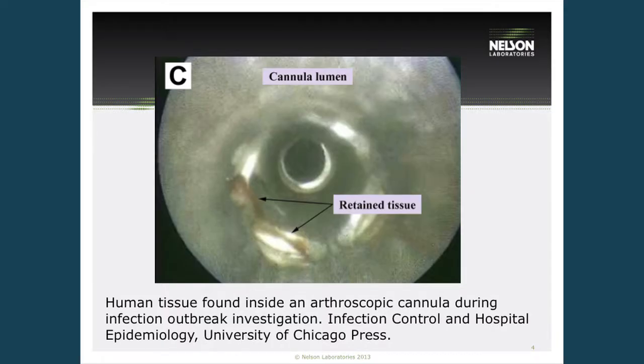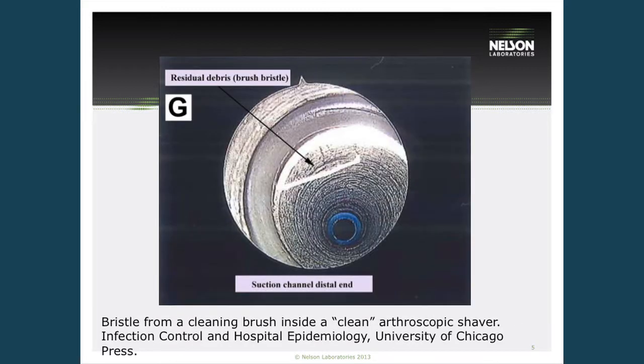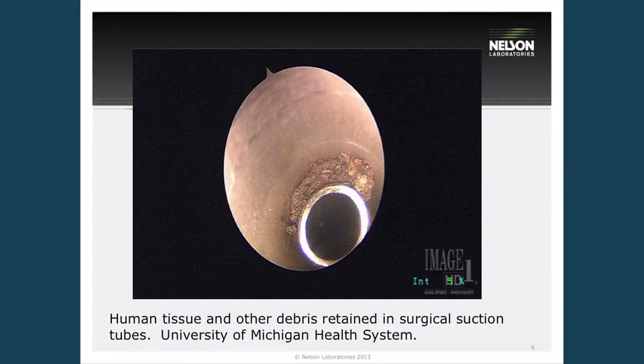So we see a lot of issues in healthcare facilities of not being able to fully clean medical devices. And this comes for many reasons. Whether the validation is performed appropriately, and also whether the healthcare facility can perform the cleaning procedures that are necessary for reusable medical devices. Here's a picture of human tissue that was found in an arthroscopic cannula. Here's a picture of a bristle that was found inside an arthroscopic shaver. So that shows that the cleaning process was performed, but in that process, a bristle was dislodged from the brush and was never removed during the rinsing process or the rest of the cleaning process.